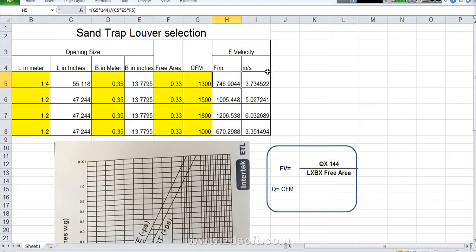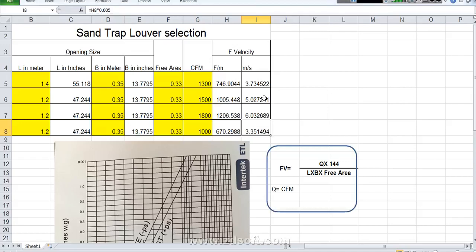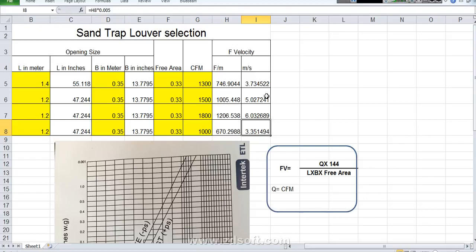Then as I told you the next point is sizing. How we will do the sizing. For example this velocity you can find here. See it is 3.5 or 3 meter per second. This face velocity should not exceed more than 5 meter per second. If it is exceeding more than 5 meter per second there is noise or sound will come. You may notice this one. The sound will be too much. If this 3 meter per second to 3.5 meter per second is the comfortable point actually for this face velocity.